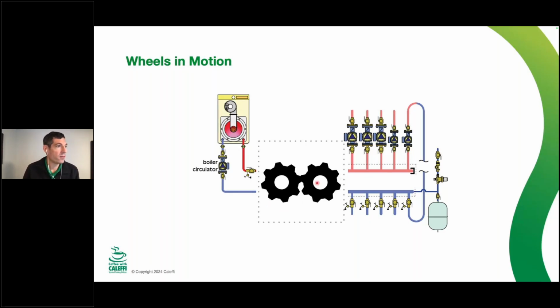Now, if we use that same analogy here, let's say we've got 5 circulators on here that are going through distribution to this building, but we just have exactly what we need going through that boiler heat exchanger. These two are in conflict here. So if this is just straight through piping, we have two different flow conditions required on the right side and on the left side. And if they're in conflict, somebody loses here. We're either going to have too much flow through the boiler, too little flow through the boiler in some scenarios. That won't work.